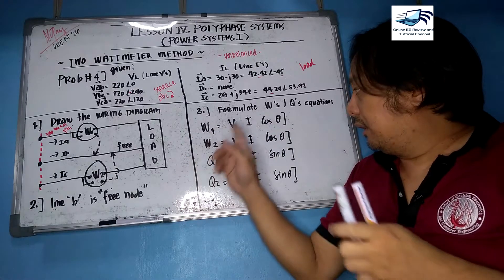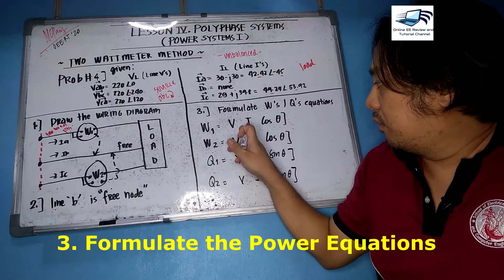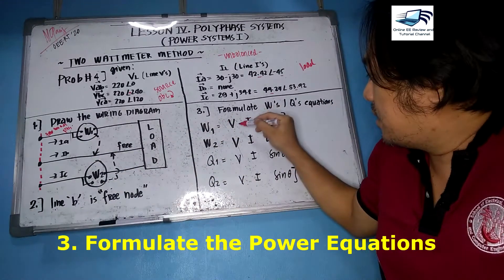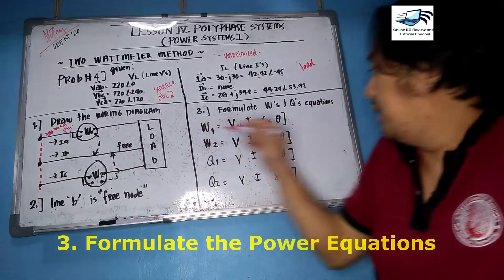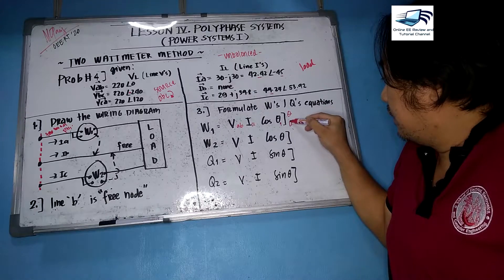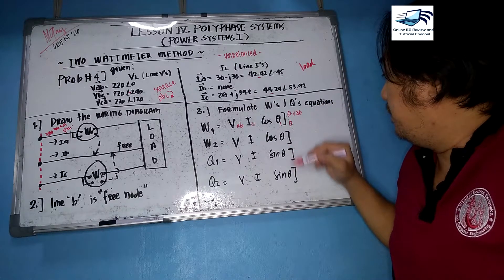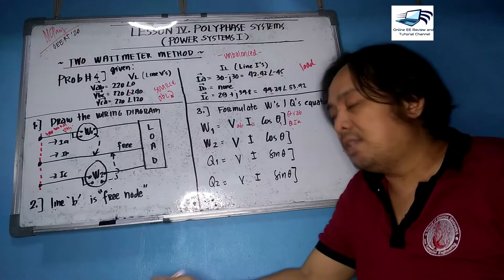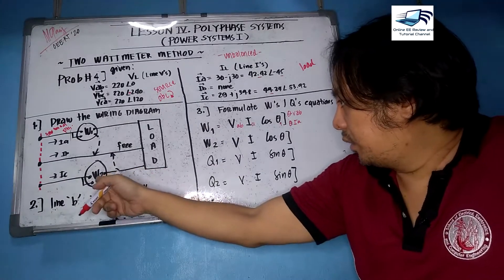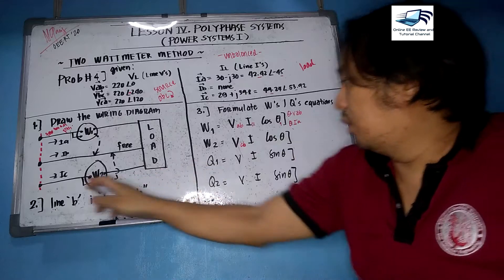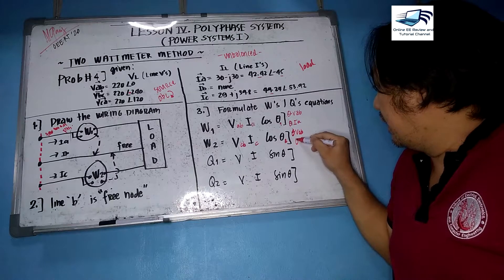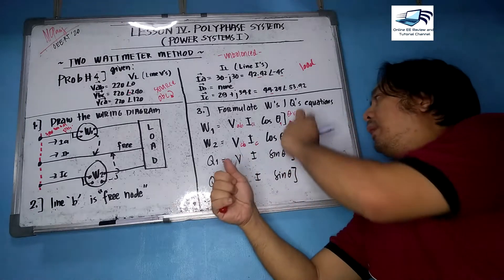Let us have the wattmeter readings. The voltage coil of wattmeter one is connected A to B, so we have Vab, and you have your line current Ia. This gives angle theta one, which is dependent upon the angle displacement of voltage Vab and current Ia. For W2, the connection is Vcb, so you have line current Ic and angle theta two, which is dependent upon the angle of Vcb and the angle of current Ic.